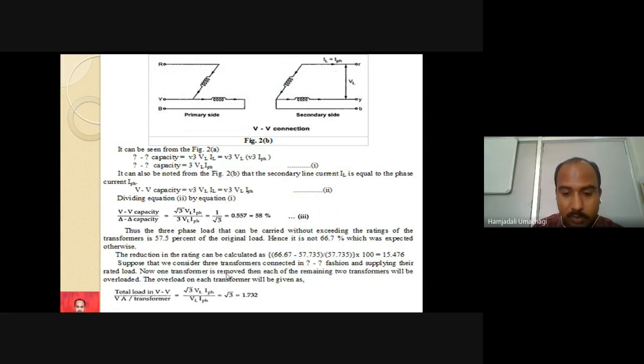Okay. Suppose that we consider 3 transformers connected in delta-delta fashion and supplying their rated load. Now one transformer is removed, so each of the remaining 2 transformers will be overloaded, yes or no? When the connection is in delta-delta fashion, then it can carry the load safely, 100% of the load. But due to some fault, if any one of the transformers goes out of service, or if it is removed, then the 2 transformers are overloaded, yes or no? Because now whatever load was earlier carried by 3, that whole load has to be carried by only 2 transformers, and the 2 transformers may get overloaded. So what is the overload that can be carried by the other 2 transformers, that we can calculate here.